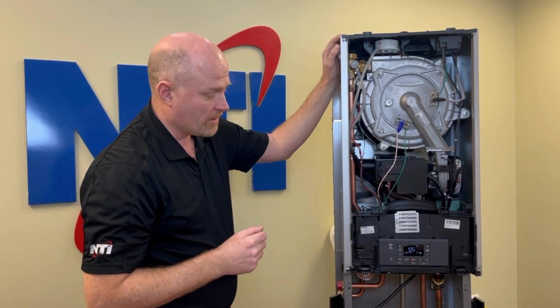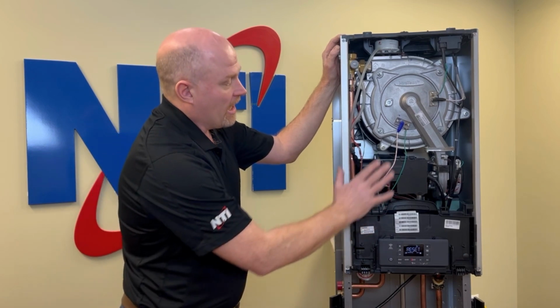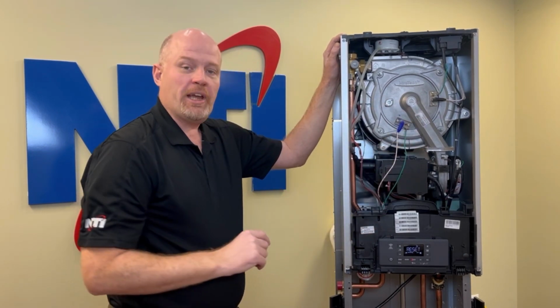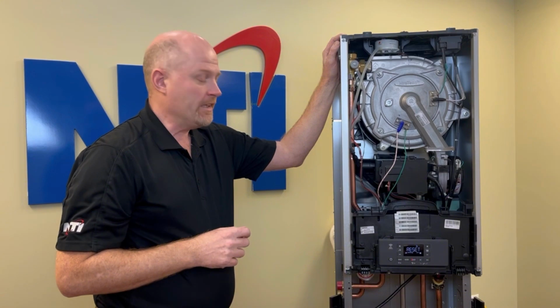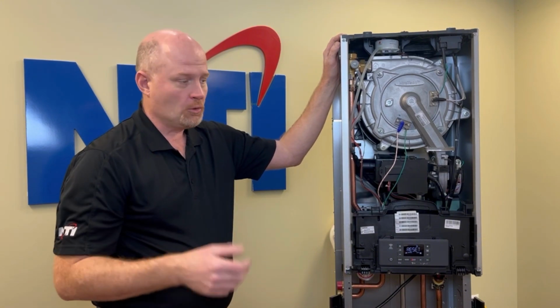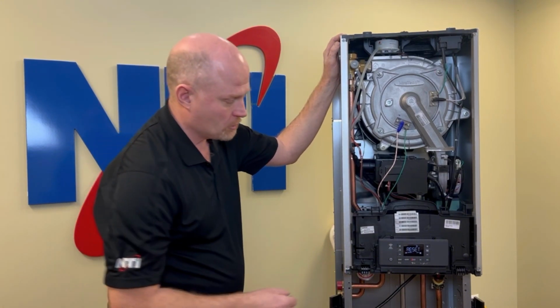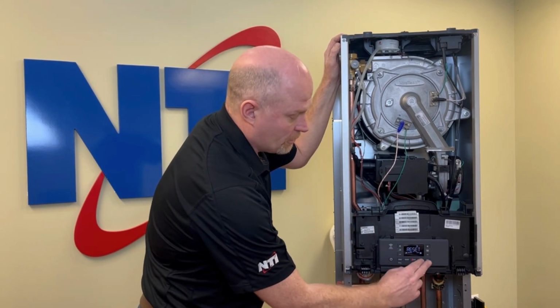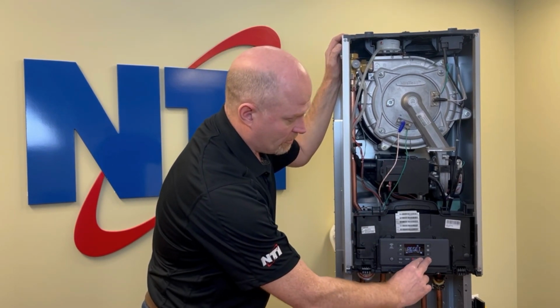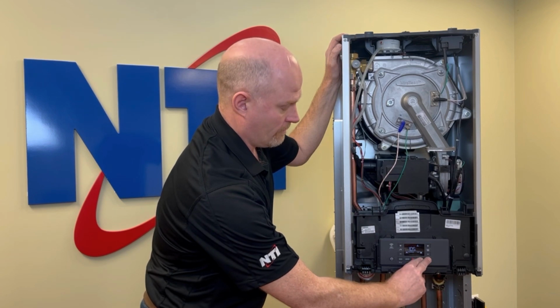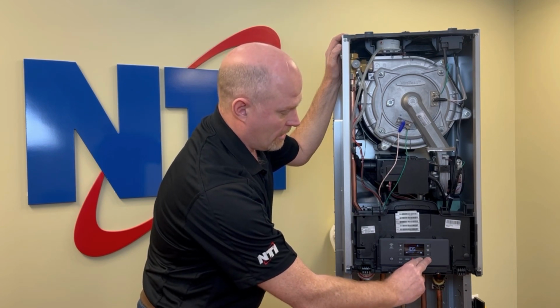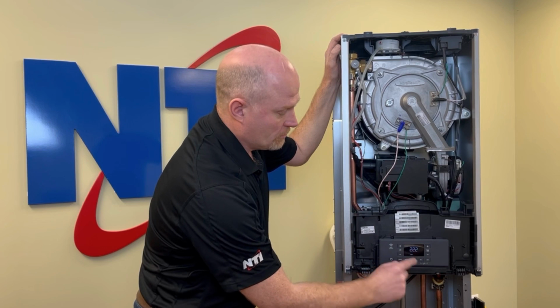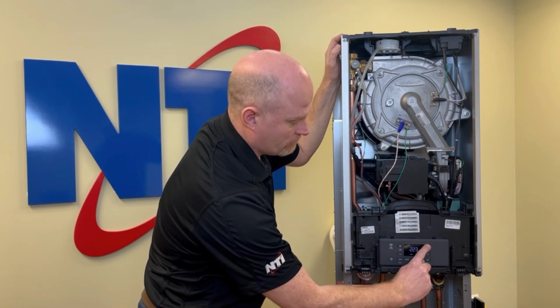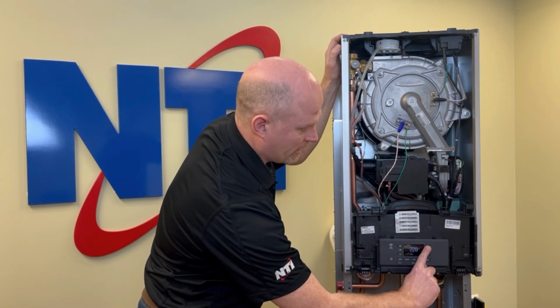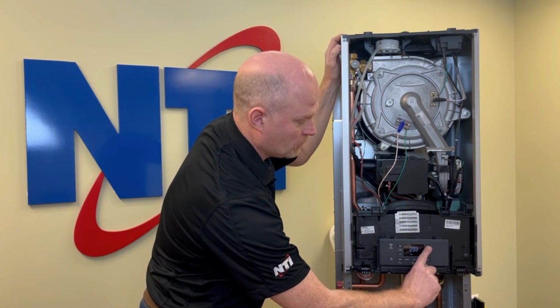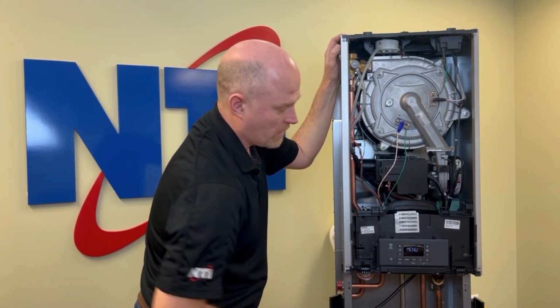Now, there's a very important thing to check on this code. If you have no overheat situation and you're only seeing 105 in the error history, it may indicate that you've got an older version of software and need to upgrade the control board. To do that, press and hold OK and escape at the same time. After about 5 seconds, 222 comes up on the screen and the word code. Use the plus button to enter the code 234 and press OK.